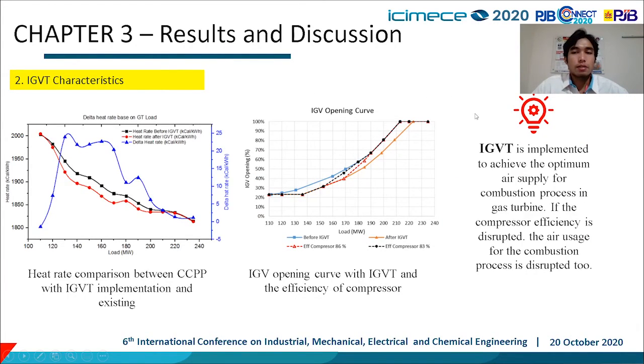The IGVT characteristics. The IGVT is implemented to achieve the optimum air supply for combustion process in gas turbine. If the compressor efficiency is disrupted, the air usage for the combustion process is disrupted too. In this figure, it shows the comparison between the combined cycle power plant heat rate after and before IGV tracking is implemented. It shows that the heat rate after IGVT implementation is lower than before the implementation. The heat rate reduction begins from 120 megawatts.